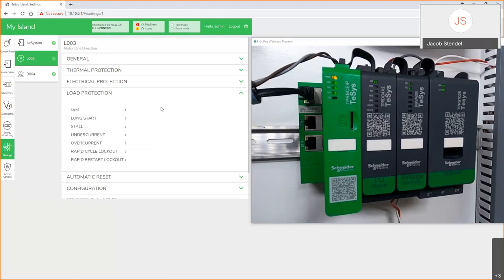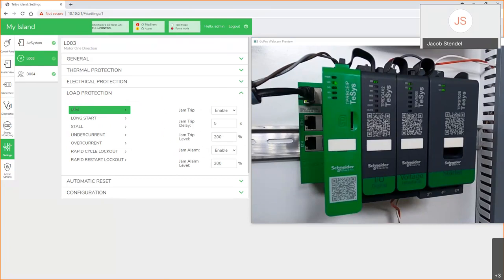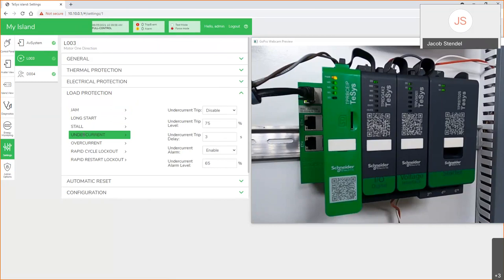Load protection is really where all the important adjustable set points for protection come into play. You can configure the level, how long it takes before it trips, and also tell it how often to restart, the restart counter. You can have it restart for load, but if it's an electrical problem, don't try to restart, just trip out. These are all configurable. Maybe there's a time where you don't want it to trip in 3 seconds because you know that conveyor takes 10 seconds to get up to speed based on the load it hits. Well, you just set that to 10 seconds, and then you set your percentage of the FLA of what you want it to report back.